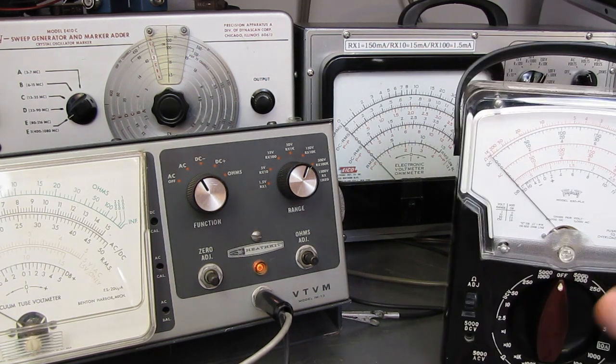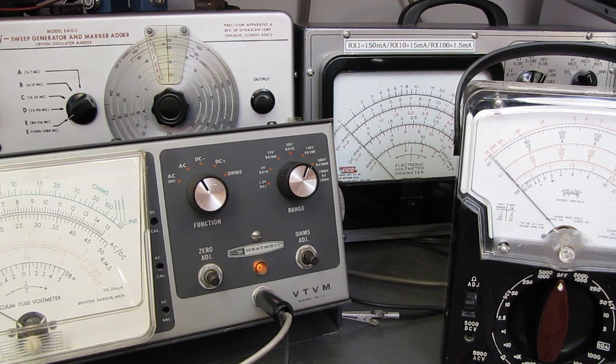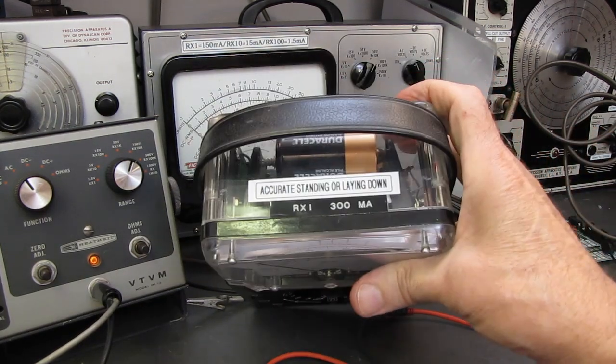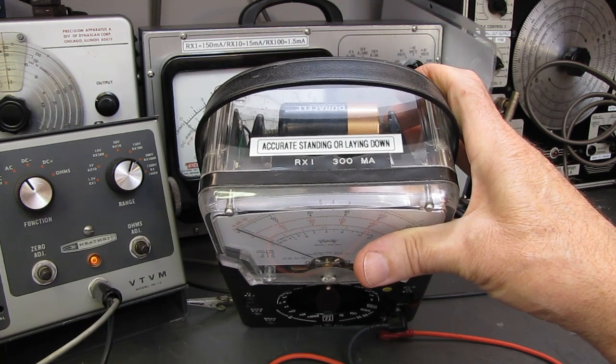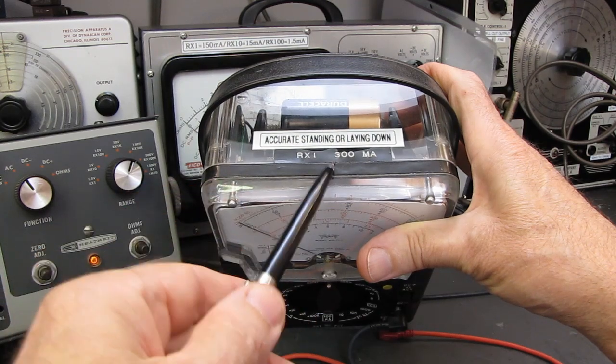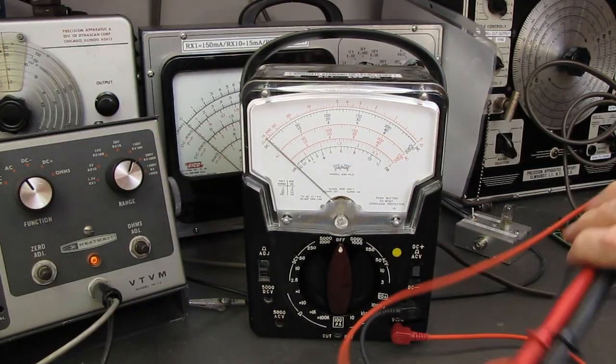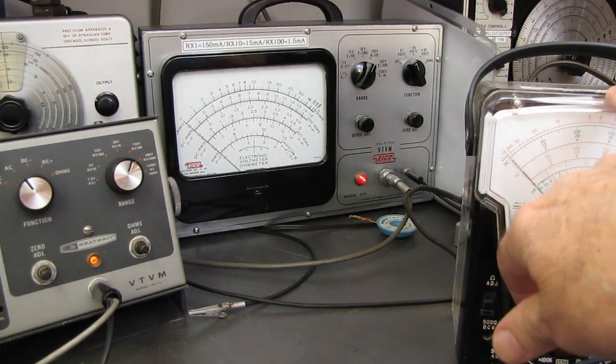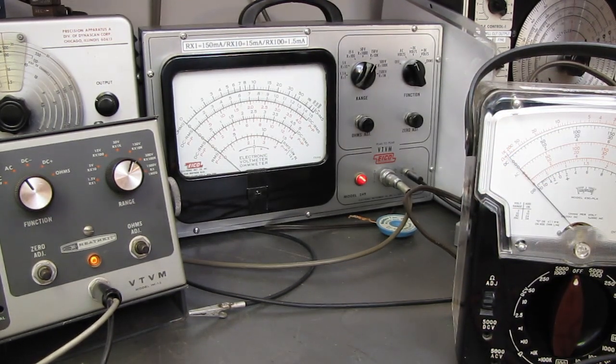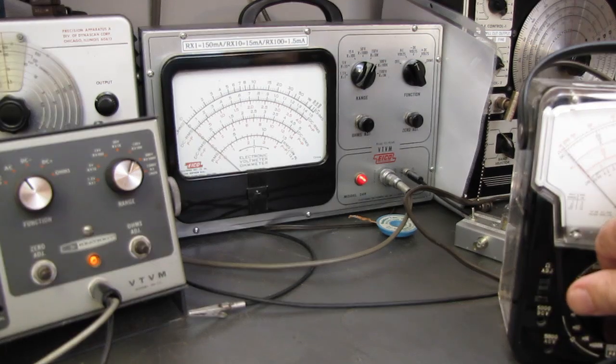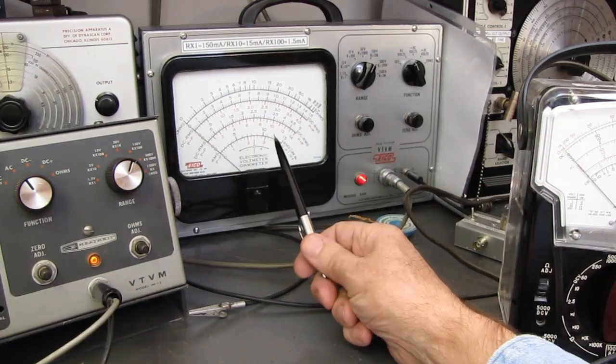If you were to put this on R times 1 setting and test those fuses, you'll have a whole box of bad fuses. They'll all test bad because you'll blow every one of them. Because on R times 1, this passes 300 milliamps through the probes. It would be 30 milliamps on R times 100 and 3 milliamps on R times 1000. Or excuse me, R times 10 would be 30 milliamps. R times 100 would be 3 milliamps.